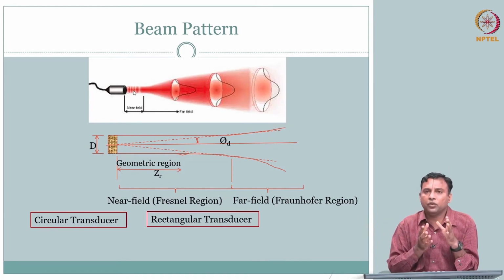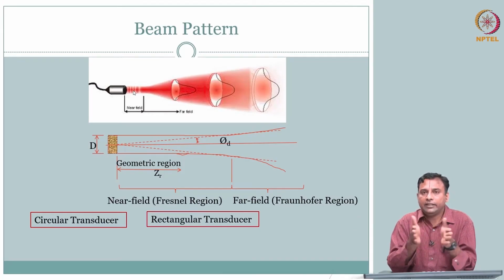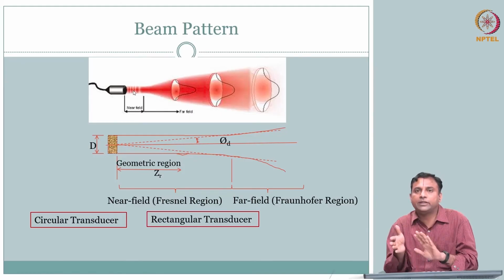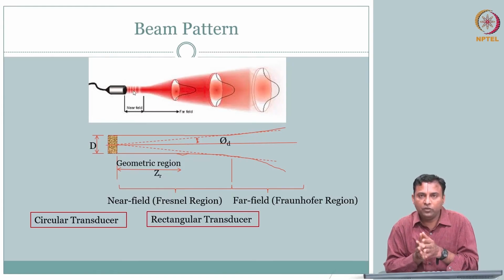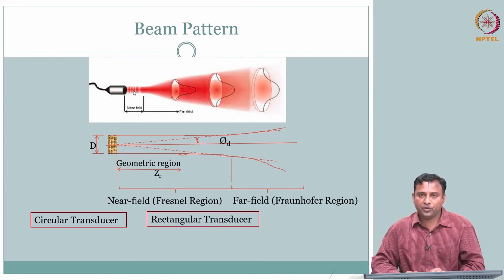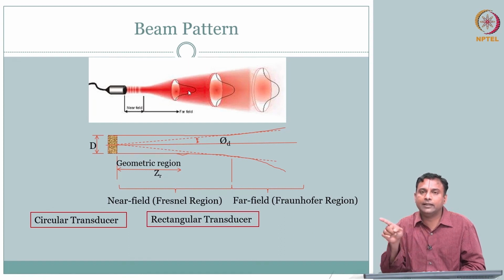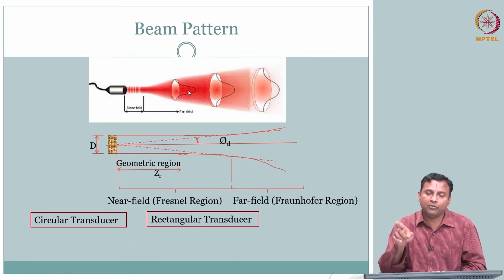So here also, even though we have engineered the transducer to predominantly do this, the moment the wave comes outside the transducer, its inherent nature is to diverge. So the pressure wave, when it is diverging, will have an intensity that is different whether you are situated along the center or moving away from the center.